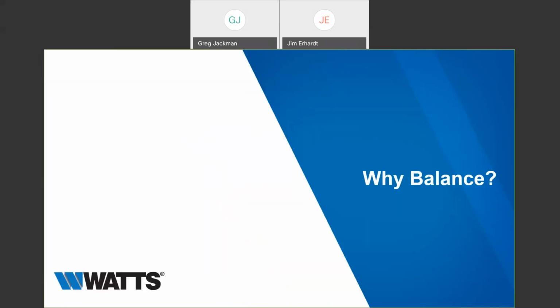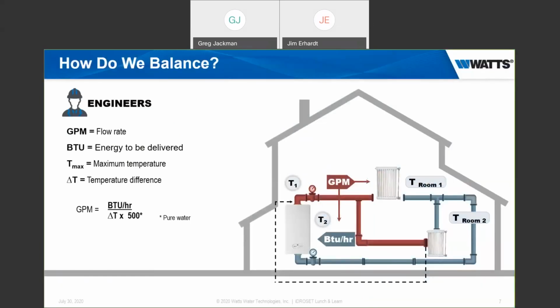So why do we need to balance a system? And this all starts really for a typical commercial application. It is going to start with the specifying engineer. If you look on the bottom left of the screen, you'll see an equation that reads GPM, gallons per minute, equals BTUs per hour over delta T times 500. So the gallons per minute, of course, is the actual flow rate that the iDROSET measures, and that's measured as part of the balancing process.